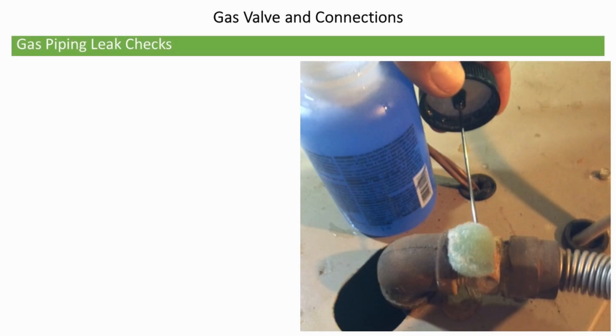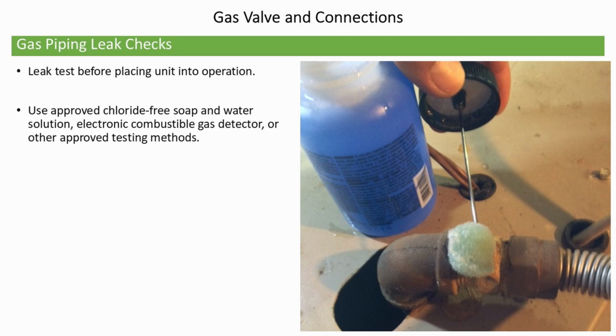Gas piping leak checks. Leak check before putting any unit into operation. Use an approved chloride-free soap and water solution, electronic combustible gas leak detector, or other approved testing methods. Warning: never use a match or open flame to test for leaks.